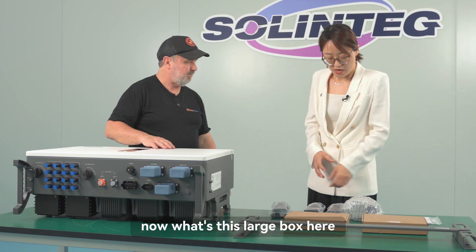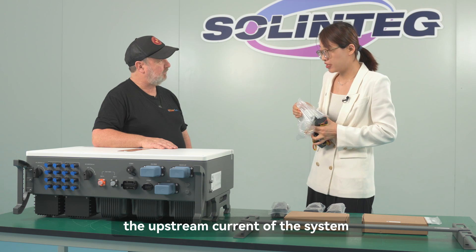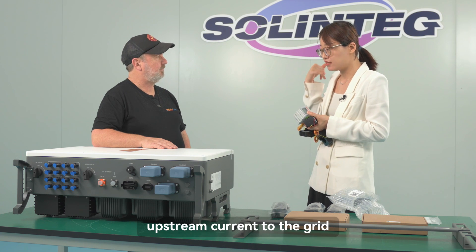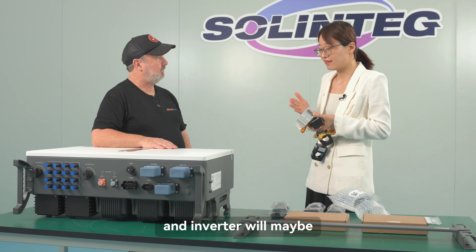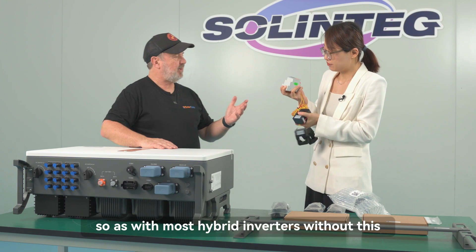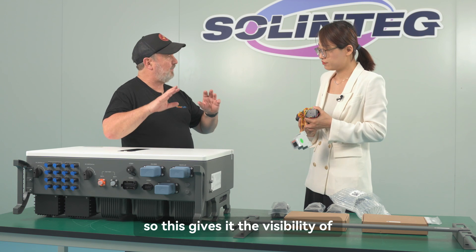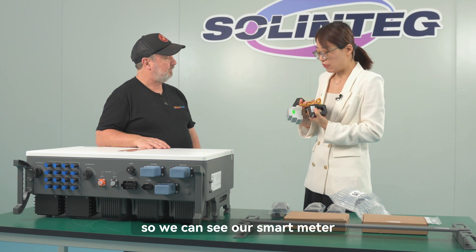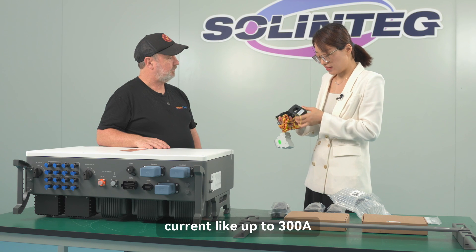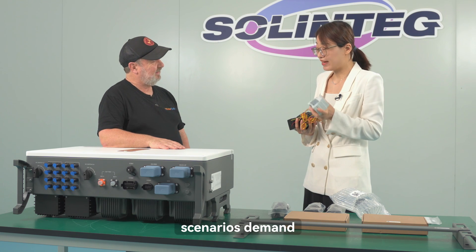This larger box contains our smart meter. The smart meter detects the upstream current of the system. When the meter detects current flowing to the grid, it signals the inverter to stop or decrease power generation to ensure there is no excess power exported. Our smart meter has three integrated CTs, each rated up to 300 amperes — that should meet most scenarios and demand.